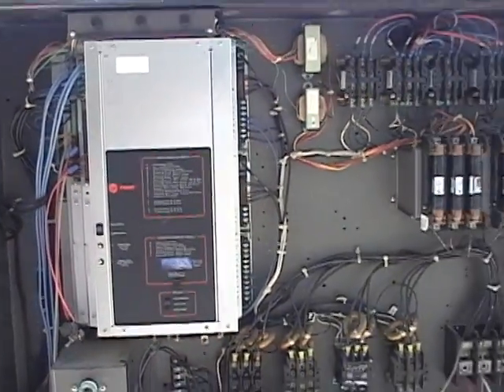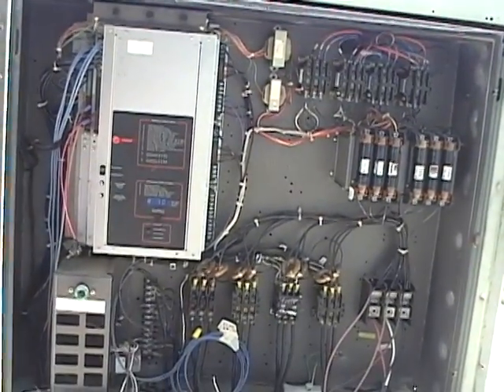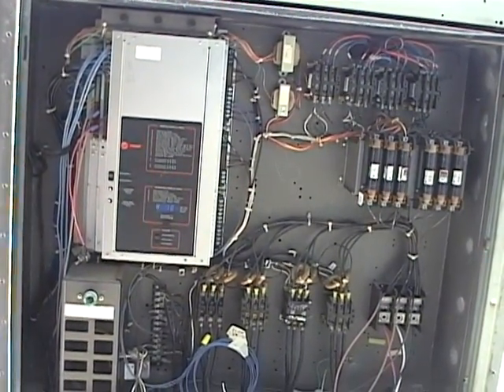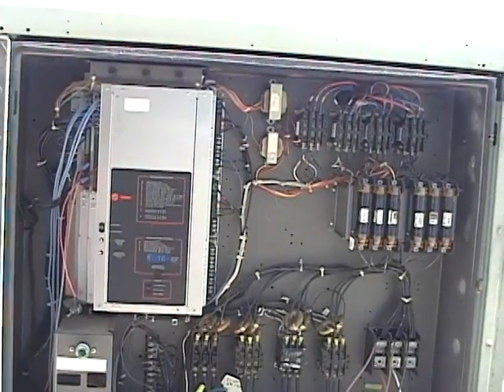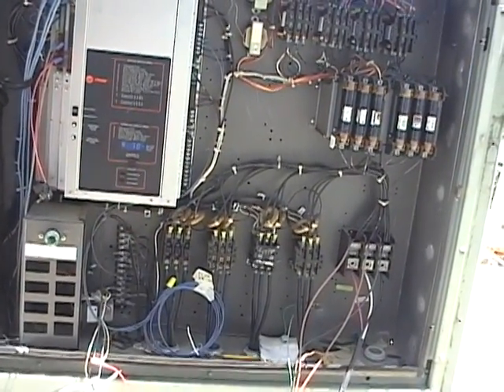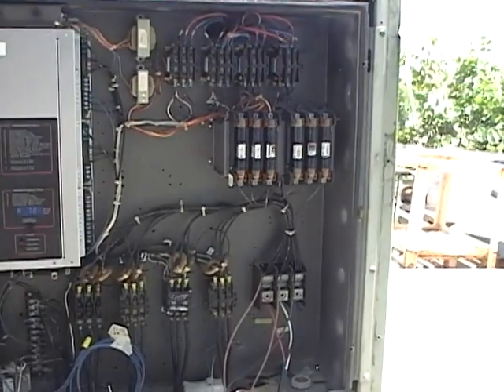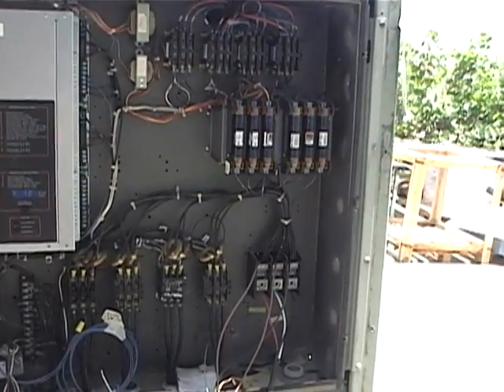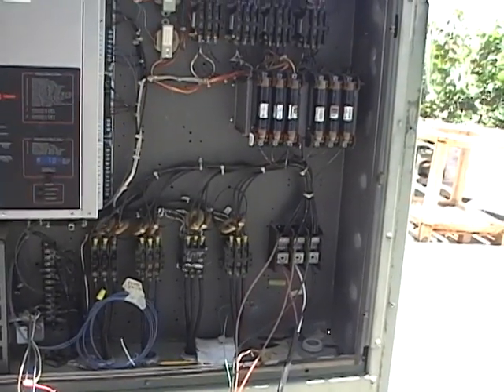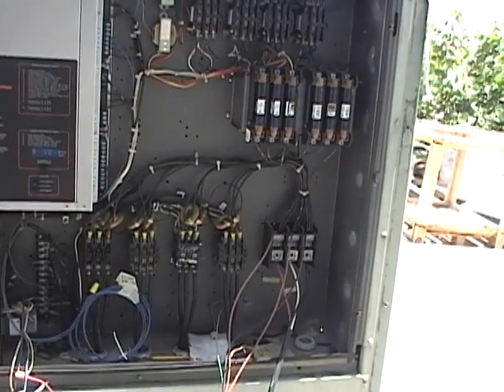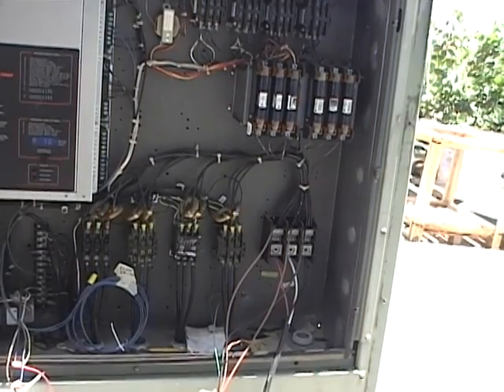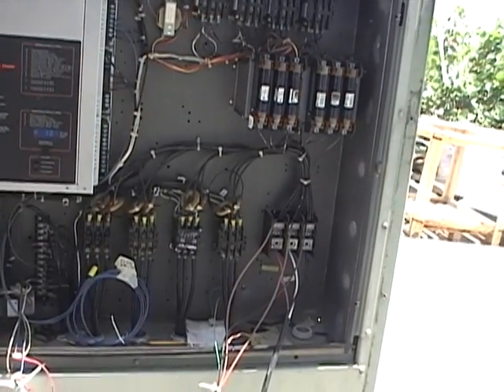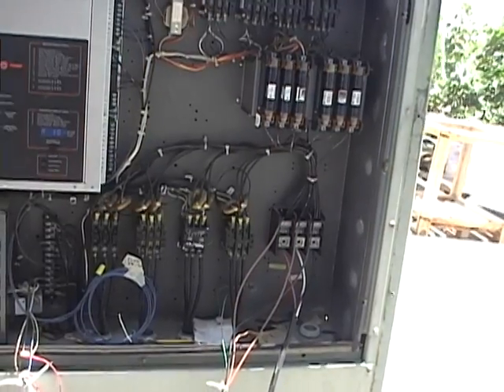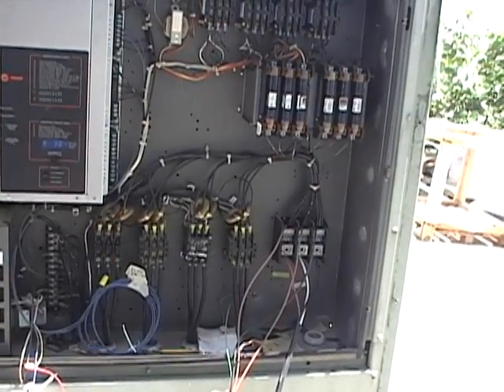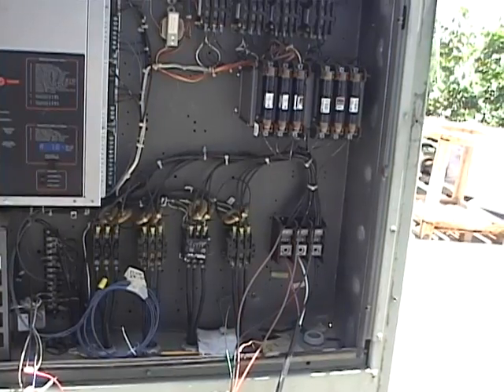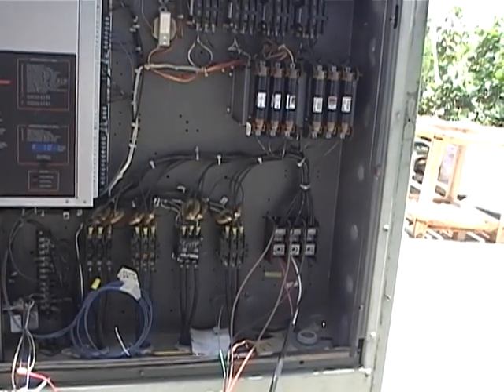It takes a while for this unit to warm up. Remember, the compressors themselves actually have to physically warm up and get up to temperature before it'll actually allow them to fire. This unit is designed so that it runs 10, 20, 30, it'll run 1 compressor, then 2 compressors, then 3 compressors, then 4 compressors as needed. It only runs the compressors as needed. If it doesn't keep up with itself, it'll fire more compressors to keep the unit running more. So it only pulls in as much as it needs in order to maintain what it has to for its capacity, so that she runs and doesn't waste all the electricity to run all the compressors. She'll pull them in as she needs them.